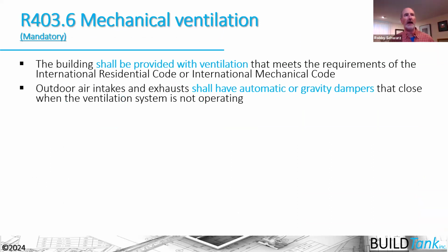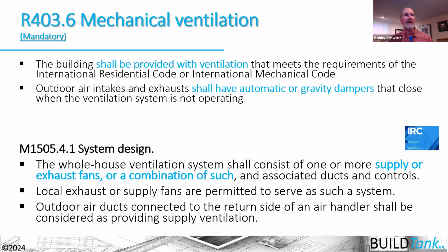Mechanical ventilation has to be provided, and it has to have some type of gravity damper if you have a dedicated duct to the outside that will open and close when that duct is bringing air into the house. And then we're also allowed to use either a supply and exhaust or a combination or balanced ventilation system in our houses there.